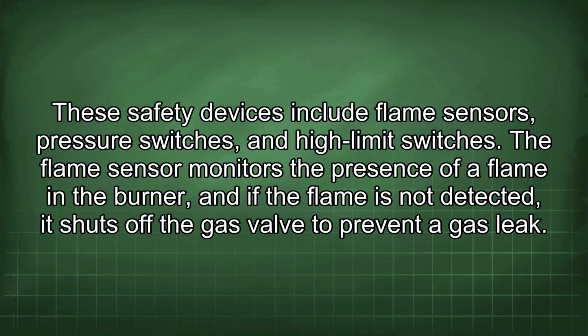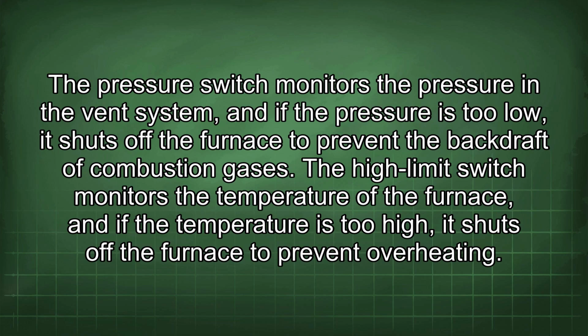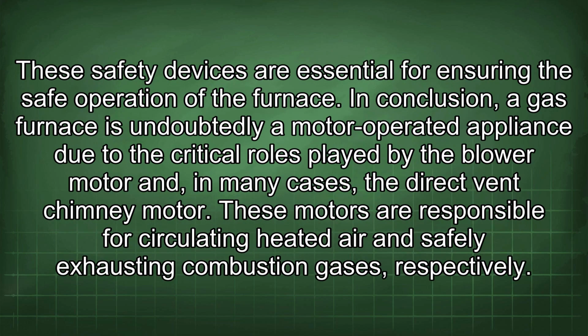The flame sensor monitors the presence of a flame in the burner, and if the flame is not detected, it shuts off the gas valve to prevent a gas leak. The pressure switch monitors the pressure in the vent system, and if the pressure is too low, it shuts off the furnace to prevent the backdraft of combustion gases. The high limit switch monitors the temperature of the furnace, and if the temperature is too high, it shuts off the furnace to prevent overheating. These safety devices are essential for ensuring the safe operation of the furnace.